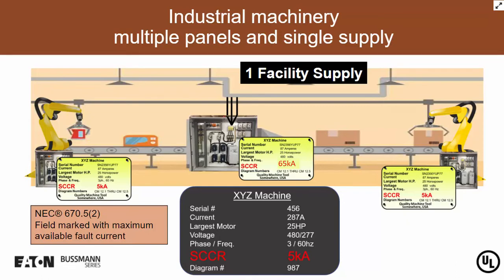So let's take a look at a couple of examples here that can be a bit challenging. Here we have multiple panels with a single supply. The first thing we have to determine is to look at the circuit diagram. Do we have a main panel that's feeding the other panels? In other words, are those other panels sub-panels, or are all the panels being fed from the same supply where they're all essentially electrically connected at the line terminals? So if we have a situation where we have sub-panels, those sub-panels may have a short circuit current rating less than the main panel, as we see in the example here. So if we don't do anything more than using the weakest link method, obviously the short circuit current rating for the machine then defaults to 5,000 amps. If we need a higher rating, if that 65 kA rating is important, what one could do is do a study on the machine itself to determine what the available fault current is at those sub-panels. It can be done.